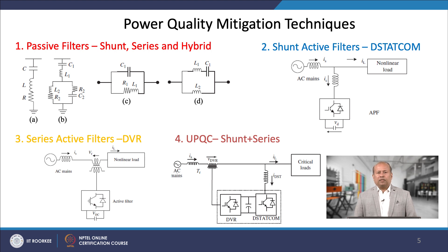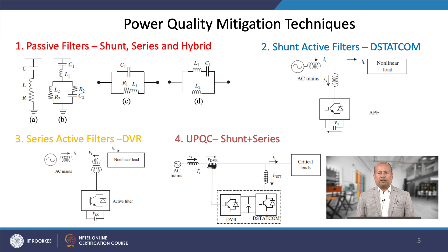The first mitigation technique is passive filters, which may be shunt type — as seen in figures a and b — or series type — as seen in figures c and d — or hybrid type, which is a combination of both shunt and series. These filters consist of reactive elements such as inductors and capacitors, with and without switching. In high voltage AC and DC transmission systems, passive filters are much in use due to their low cost, simplicity, robust structure, and reactive power compensation at the fundamental frequency.